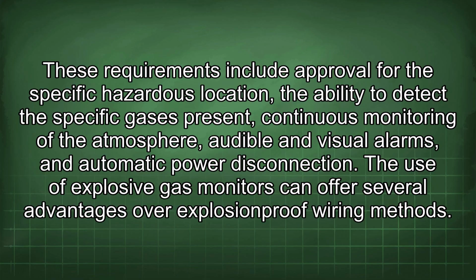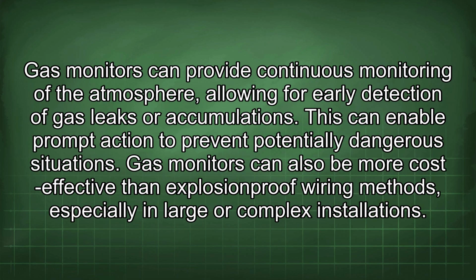The use of explosive gas monitors can offer several advantages over explosion-proof wiring methods. Gas monitors can provide continuous monitoring of the atmosphere, allowing for early detection of gas leaks or accumulations. This can enable prompt action to prevent potentially dangerous situations. Gas monitors can also be more cost-effective than explosion-proof wiring methods, especially in large or complex installations.